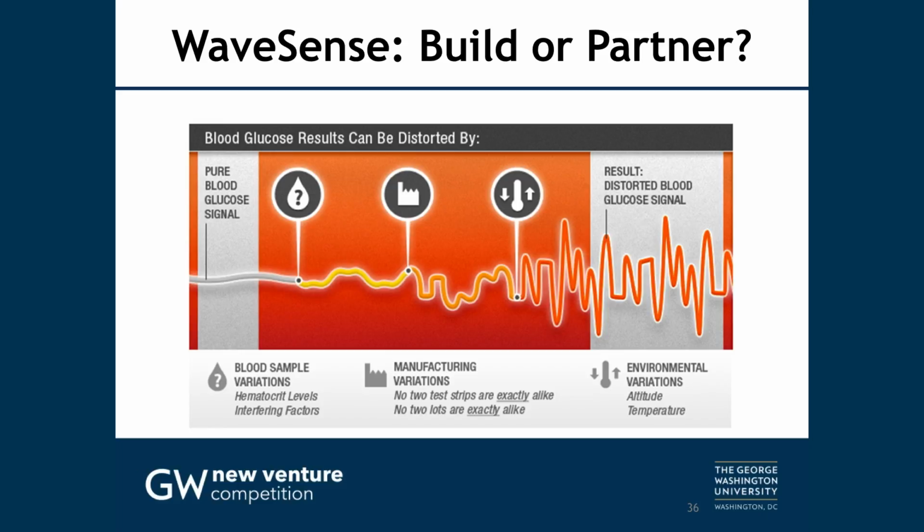The technology that was developed by the team was around dynamic signal processing. So the ability to apply multiple test voltages, signals to the electrochemical sensor to get differential responses to see what kind of chemicals, whether there was blood glucose, or whether it's being blocked by vitamin C or other kinds of chemicals.